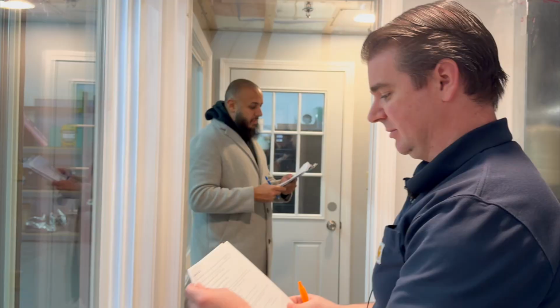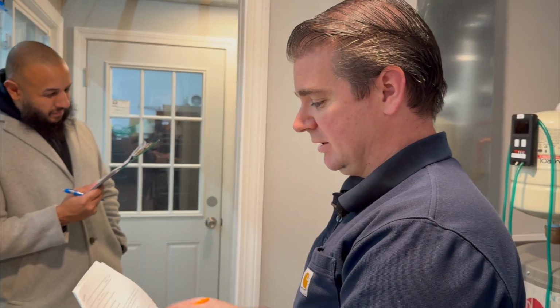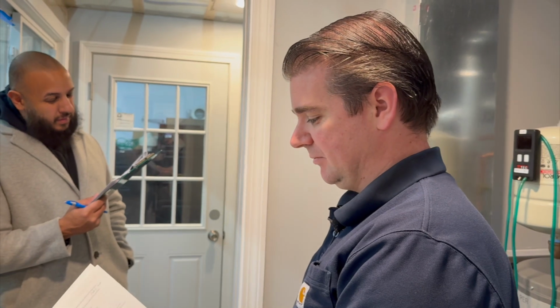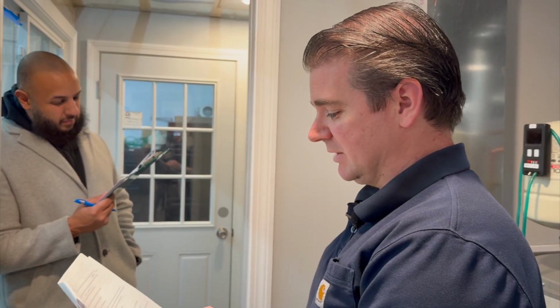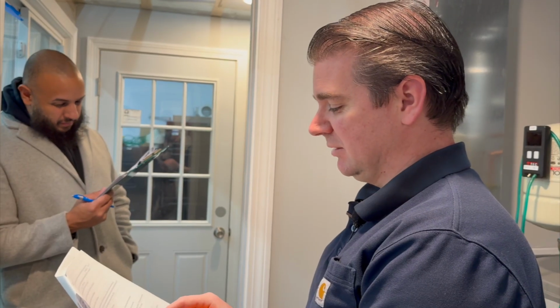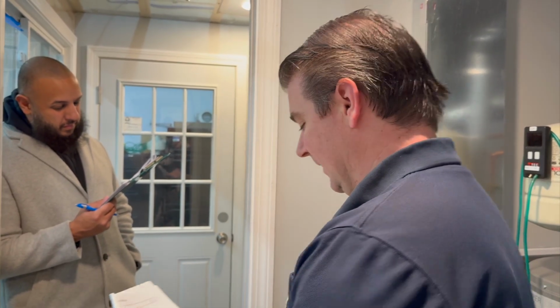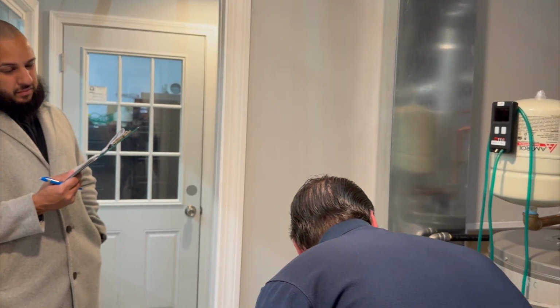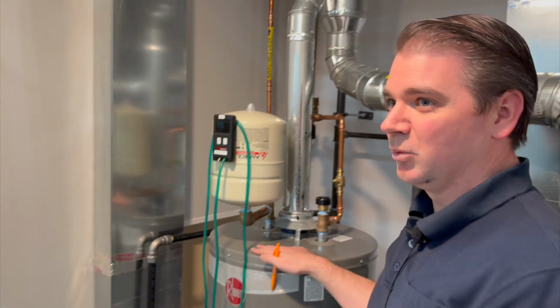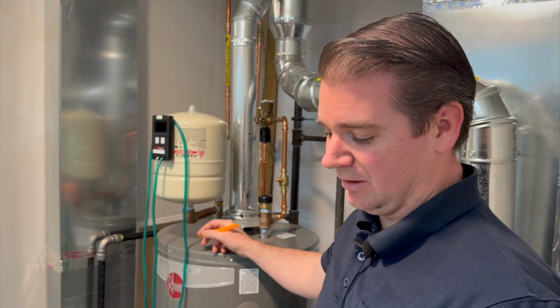Then I just want to go back to this page here real quick. I want to make sure I didn't miss anything. At number 4, we got the house set up for our testing, measured the baseline, turned on all our appliances, did the furnace, we did all that CAZ stuff. Right, it says number 11, spillage, identify the smallest input BTU appliance, and if the vent is warm or cold. Well, I guess I didn't mention that. So this one says 30,000 BTUs. This one over here is 40,000 BTUs, so this is the smaller appliance. The water heater is always considered a warm vent.